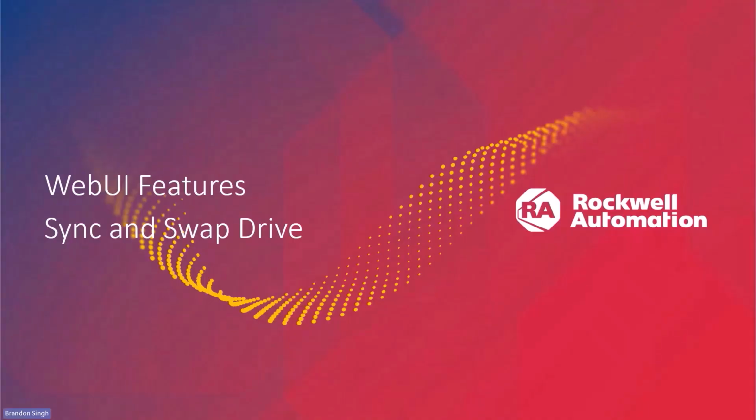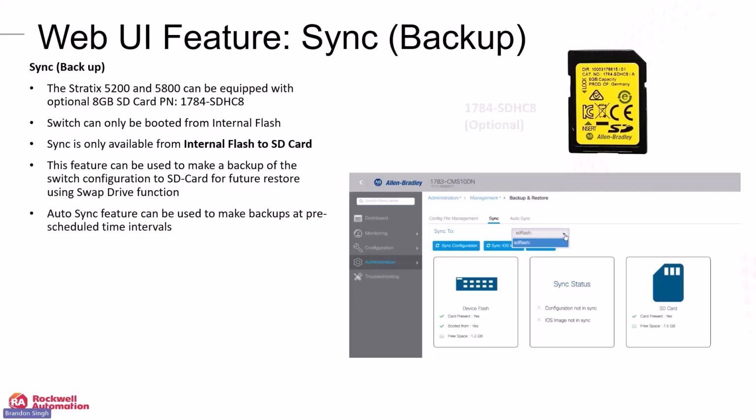One of the other changes with the web UI is as far as syncing and swap. If, for whatever reason, we need to swap out a switch because it went bad, or we need to replace a switch, the 5800 and the 5200 are available and equipped with an optional SD card, just like the 5700 and the 5400 before it. It is a different part number for the SD card. The preferred part number is 1784-SDHC8 for the high capacity SD card.